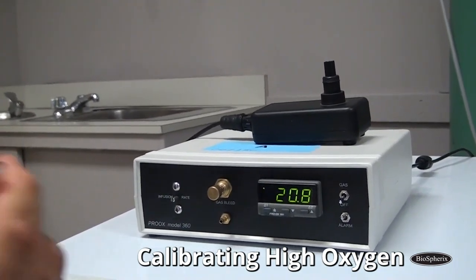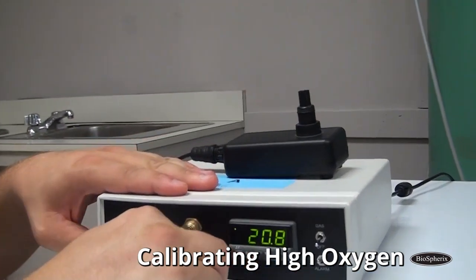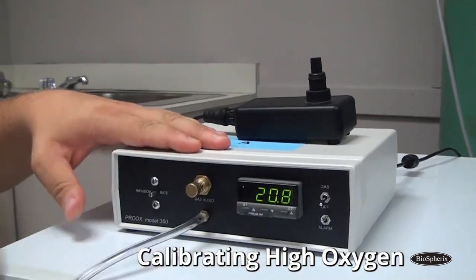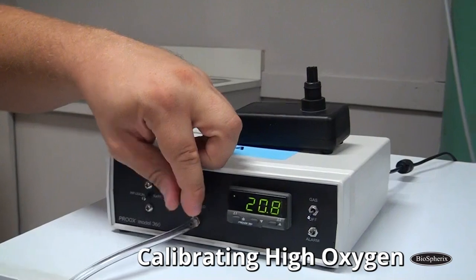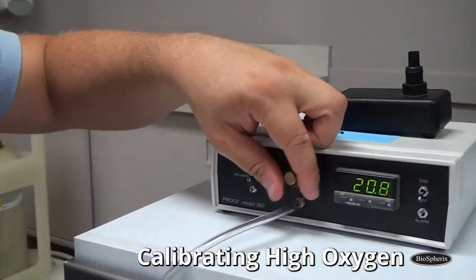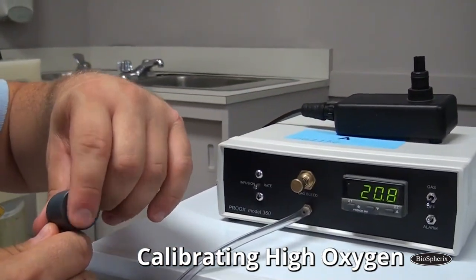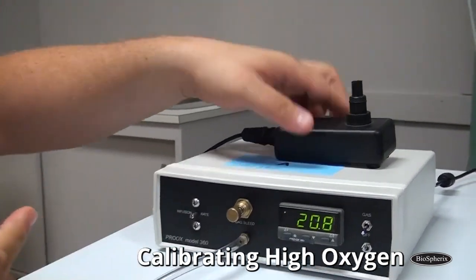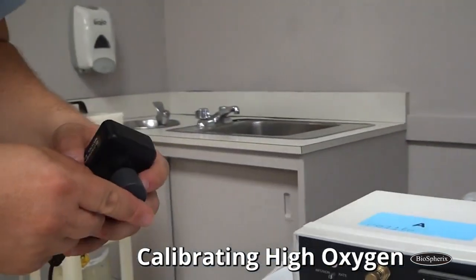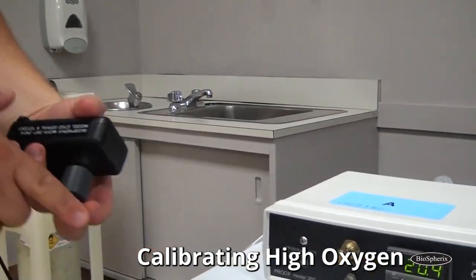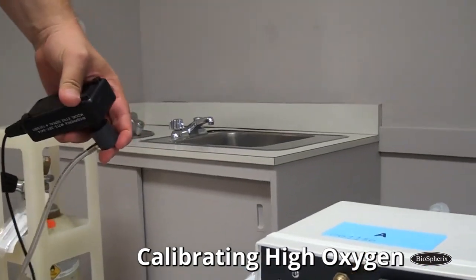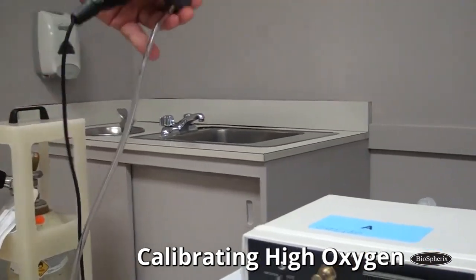I'm going to take my calibration chamber, take my tube end, put it right on the bleed valve, open the bleed valve up till you can hear it. I can hear it and feel it coming from there. And I'm going to put my sensor tip right in there and then just let it rise. Let it sit for about 2 minutes.